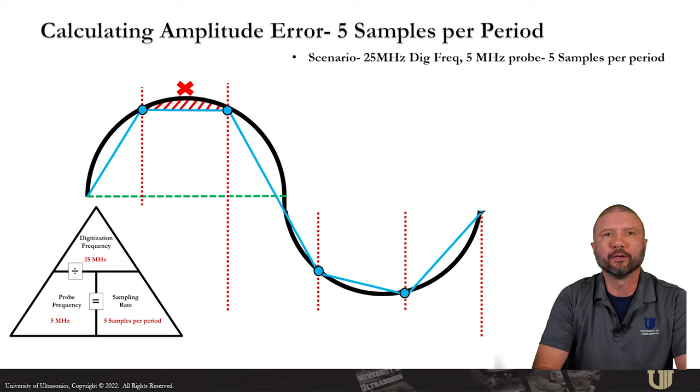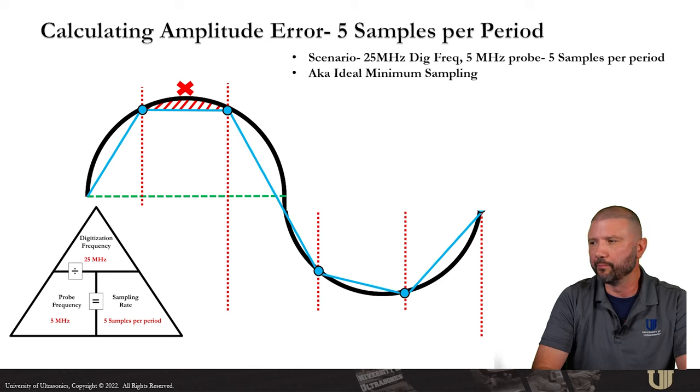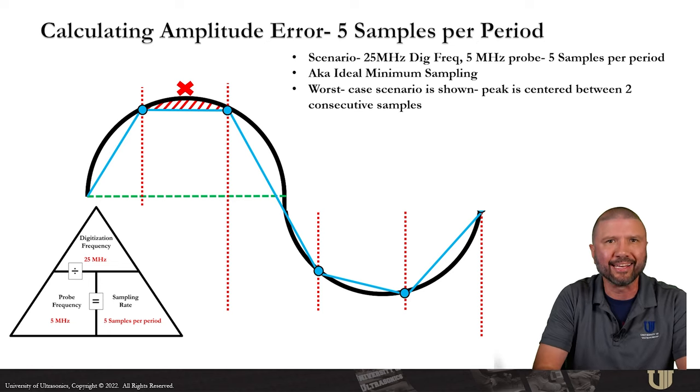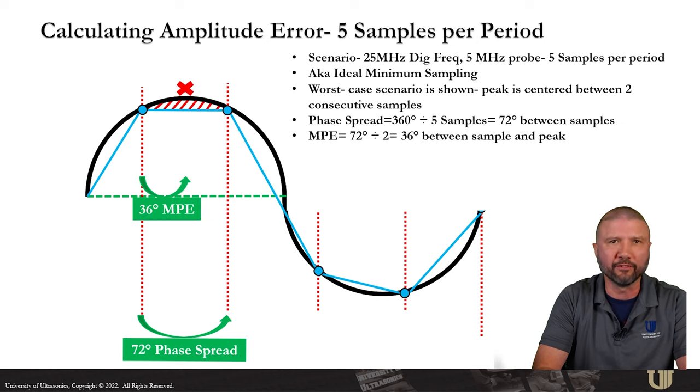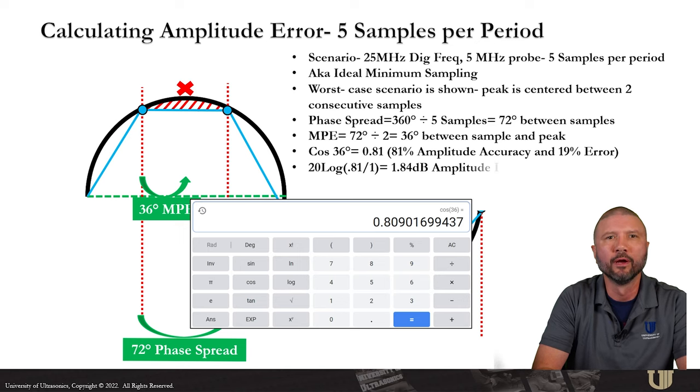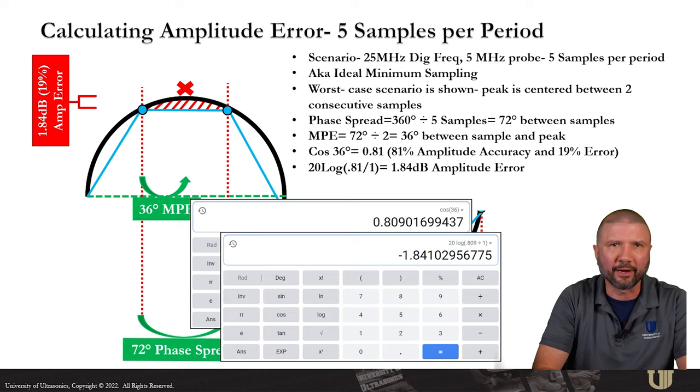Let's try another one. 25 MHz digitizing frequency with a 5 MHz probe. And that's going to give me five samples per period, aka ideal minimum sampling. Again, I've got the worst case scenario shown where the peak is centered between two samples. Phase spread is 360 divided by 5, which is going to tell me there's 72 degrees between samples. Divide that by two and I get my maximum phase error of 36 degrees between the sample and the peak. Cosine of 36 is 0.81, which tells me I've got about 81% accuracy and 19% error. And if I convert that to a dB, I get about 1.84 dBs. Five times the probe frequency, which gives us five samples per period, is the minimum digitization frequency allowed for encoded phased array in ASME Section 5, Article 4, Mandatory Appendix 5. We use this because we can keep within two dBs of amplitude error.